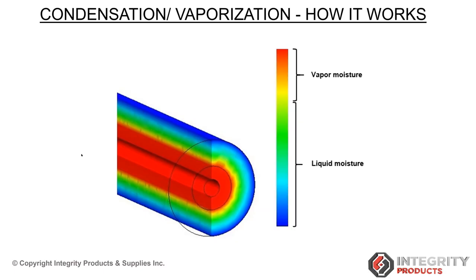Yeah, again, traditionally, I think a lot of asset owners with wet and damaged insulation would be removing the insulation and disposing of it, and then reinstalling new insulation. With the perforated dimple wrap, you have the opportunity to save that insulation. We've also been working with a lot of the major insulation manufacturers, and they have confirmed with us that once their insulation is allowed to dry out and get back into good condition, it will retain all its thermal performance as per out of the factory, out of the box, as per new. So not only from an environmental standpoint are you doing your piece, you're not disposing of wet and damaged insulation, but for a cost benefit for the asset owner, it can be really significant.